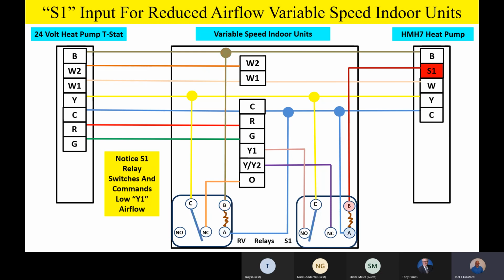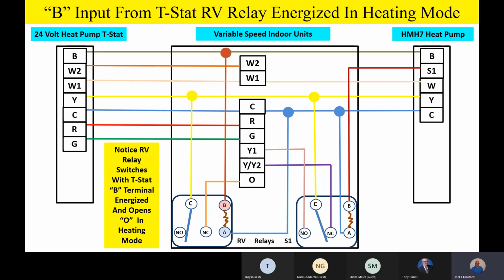Let me back that up one more time. Watch that animation right there. So we energize the RV relay in the heating mode of operation, and we break that O signal. We take the 24 volts off that O signal. So now the indoor product knows we're in the heating mode instead of the cooling mode. That's the only reason that RV relay is there, is to tell that variable speed indoor product we're in the heating mode of operation when we break that relay, or that RV relay, and we energize it with that B input for the reversing valve up above.